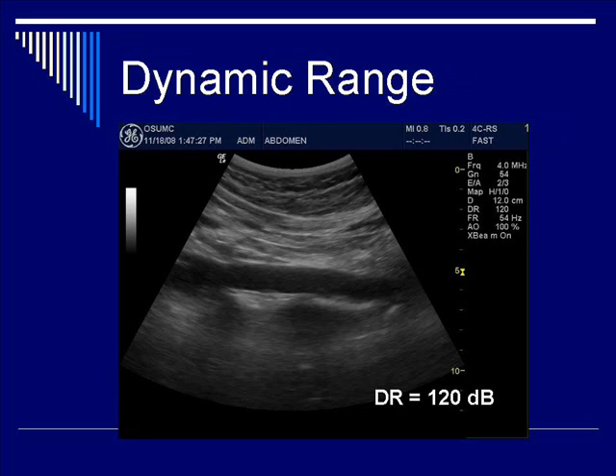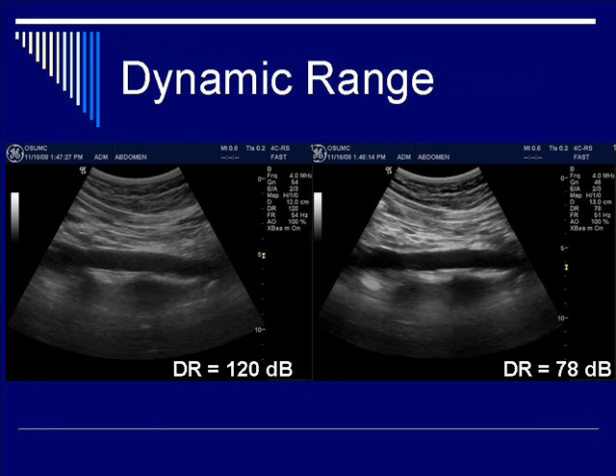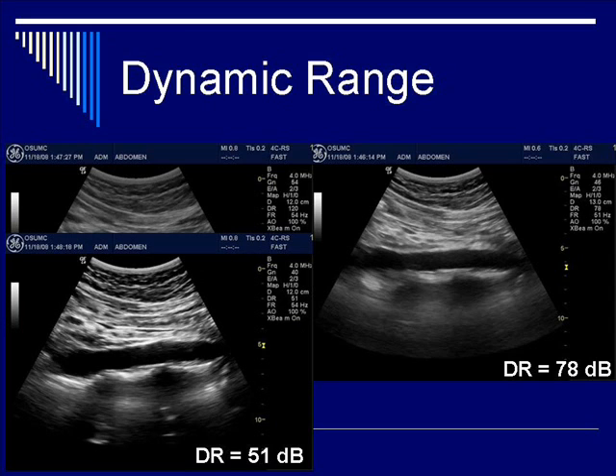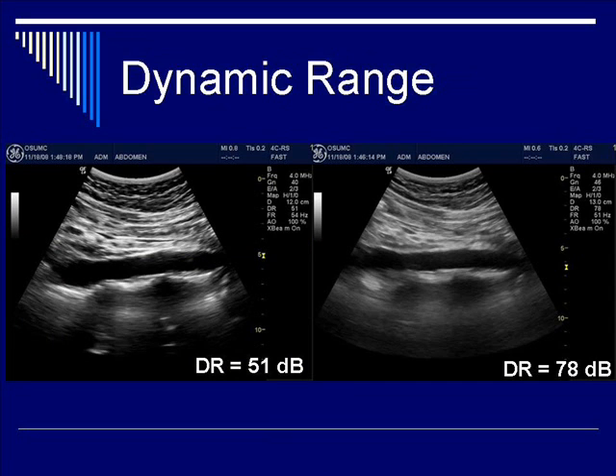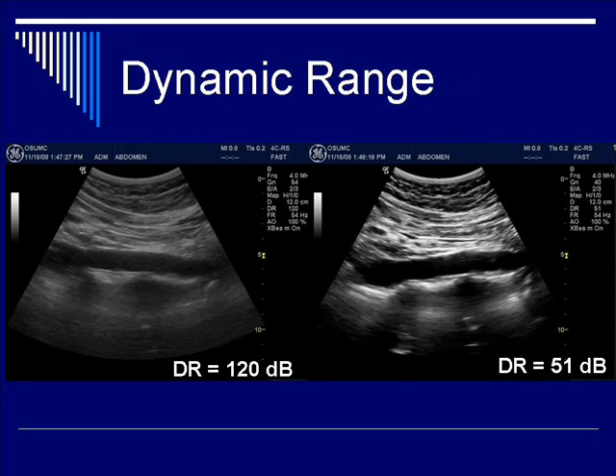Let's look at some examples. At a dynamic range of 120 dB, notice the wide range and huge gradation of grayscale. At a somewhat lower dynamic range of 78 dB, there is less gradation of gray and a little better contrast. At an even lower dynamic range of 51 dB, you have an even more black-and-white, higher-contrast picture with less grayscale gradation. Comparing 120 to 51 dB, it becomes clear that higher dynamic range gives you more shades of gray, but lower dynamic range gives you better contrast.